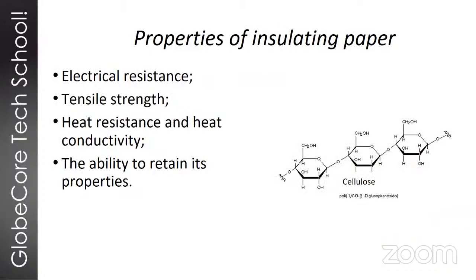So as we mentioned, the duration of transformer life is directly related to paper. So let's look at the paper in a bit more detail. The transformer paper is responsible for both physical and electrical barrier, like an insulator. If the paper becomes weakened physically, this basically causes irreparable wear of the transformer and reduction of the electric strength, which causes arcing and internal discharges, and all those discharges will cause formation of volatile and flammable gases, which will obviously cause significant catastrophic events in the transformer.